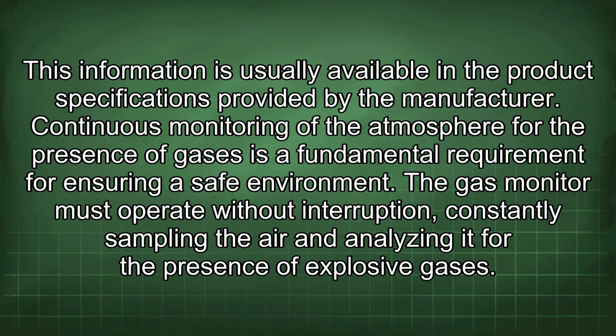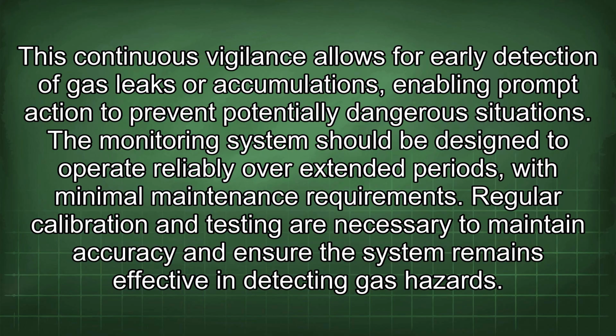Continuous monitoring of the atmosphere for the presence of gases is a fundamental requirement for ensuring a safe environment. The gas monitor must operate without interruption, constantly sampling the air and analyzing it for the presence of explosive gases. This continuous vigilance allows for early detection of gas leaks or accumulations, enabling prompt action to prevent potentially dangerous situations. The monitoring system should be designed to operate reliably over extended periods with minimal maintenance requirements. Regular calibration and testing are necessary to maintain accuracy and ensure the system remains effective in detecting gas hazards.